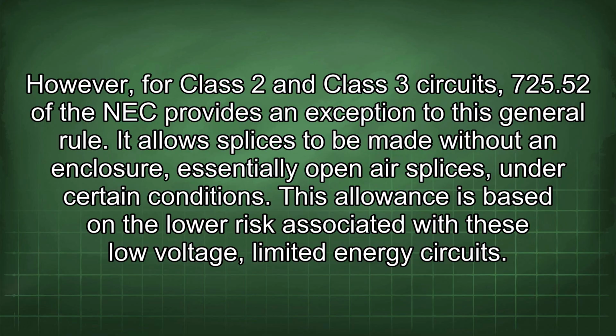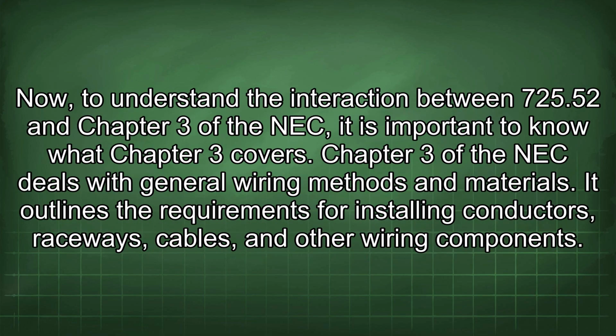725.52 of the NEC provides an exception to this general rule. It allows splices to be made without an enclosure, essentially open-air splices, under certain conditions. This allowance is based on the lower risk associated with these low-voltage, limited-energy circuits. Now, to understand the interaction between 725.52 and Chapter 3 of the NEC, it is important to know what Chapter 3 covers.